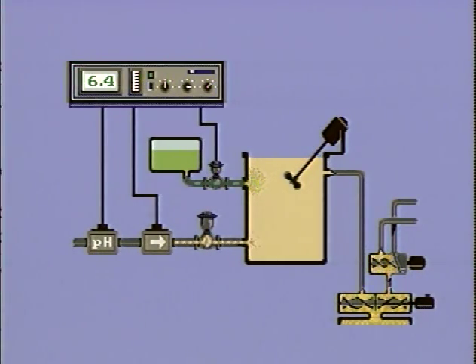In this configuration, when the pH of component B was 6.4, only a small amount of acid entered the flow. When the pH was 6.6, acid entered the flow at a greater rate. And when the pH was 6.2 or 6.3, no acid was added. Also, when the flow rate changed, the amount of acid added was adjusted to accurately maintain the pH. For 2 days after startup, the new system performed exactly as planned. The pH sensor worked, the flow sensor worked, and the valve adding acid opened and closed as necessary. The quality of the finished product was as high as ever.